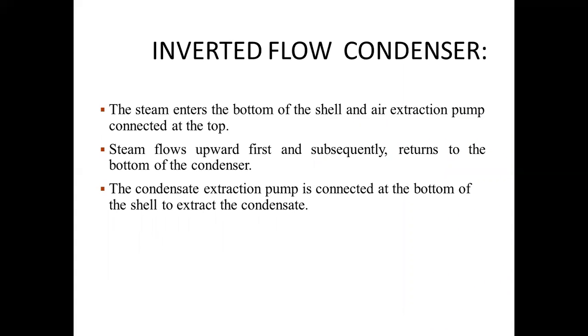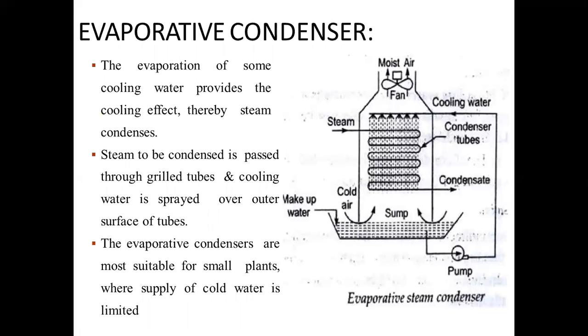Now, inverted flow condenser: the steam enters the bottom of the shell and the air extraction pump is connected to the top. Steam flows upward first and subsequently returns to the bottom of the condenser. The condensate extraction pump is connected at the bottom of the shell to extract the condensate. Next one is evaporative condenser.